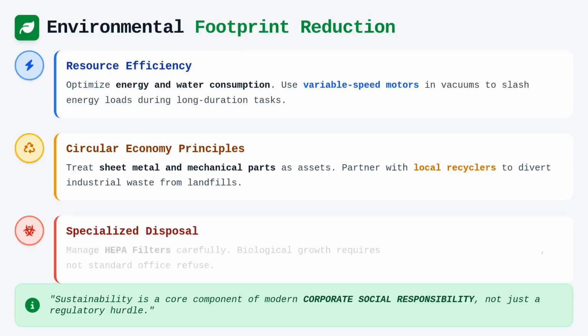Furthermore, HEPA filters represent a significant volume of waste. Ensure that you are disposing of these according to the nature of the contaminants trapped within them. If a filter is heavily contaminated with biological growth, it must be treated as biohazardous waste rather than standard office refuse.